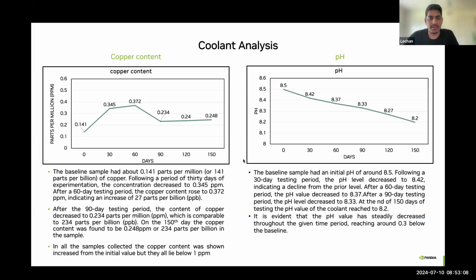lead to lower pH. But at data center level, whenever we remove some liquid for sampling, there will be fill pumps which always fill the loops back with fresh PG25 from time to time to replenish the amount drawn out for sample. There will again be addition of new corrosion inhibitors, making the pH stable over a period of time. But here, the amount of sample we are drawing out is replaced with atmospheric air. So that could be one possible reason for the reduction of pH over a period of time. Okay, thanks.